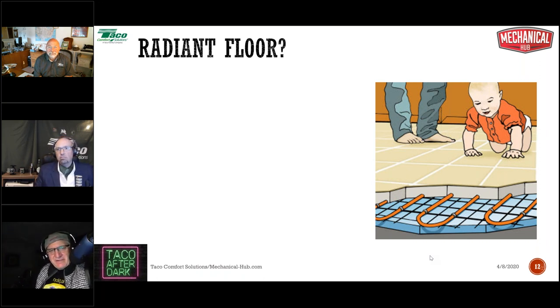My view is a little different. I think the biggest advantage to thermal mass, a concrete slab, is you have a lot of leeway to screw up the installation and still get away with it. It's incredibly forgiving. I mean, you have to go in with malice aforethought to screw up a slab job, in terms of installing the tubing and the water tank. You've got to try to mess it up. I could send you some pictures. I know there are people who have tried. I know that. I've probably seen a lot of them. But you really have to make an effort to screw it up. There's so much forgiveness. You've got leeway to miss on your water temperature, miss on your tube spacing a little bit, and get away with it.